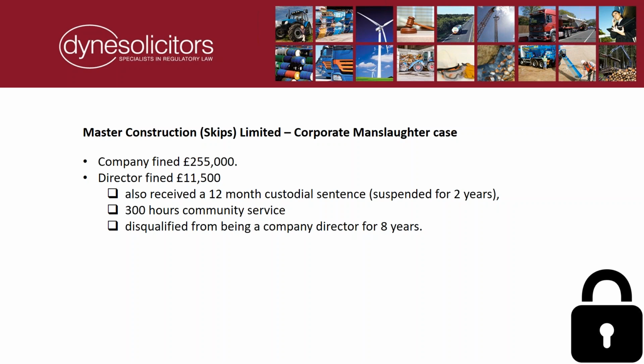There is another case, it's not on the slide, Geoff very kindly referred me to it, which is Gaskell's Northwest Limited. That was sentenced very, very recently, in fact on the 26th of October. In this case, an employee entered a baler to clear a blockage, and then the machine started automatically, resulting in the employee's death. There was an interlock, but it had been bypassed, and there was no lock-off on the machine before the clean down procedure began. The company was fined £700,000 and ordered to pay £100,000 in costs. That probably was a completely avoidable death.